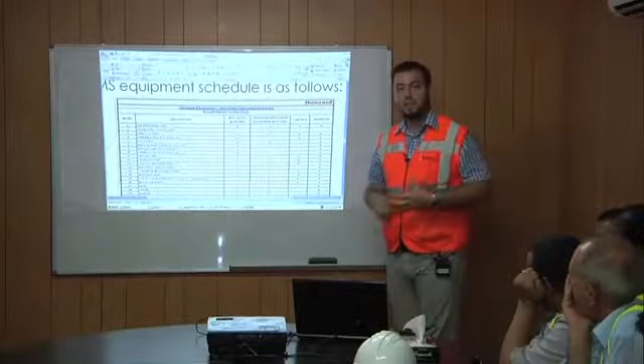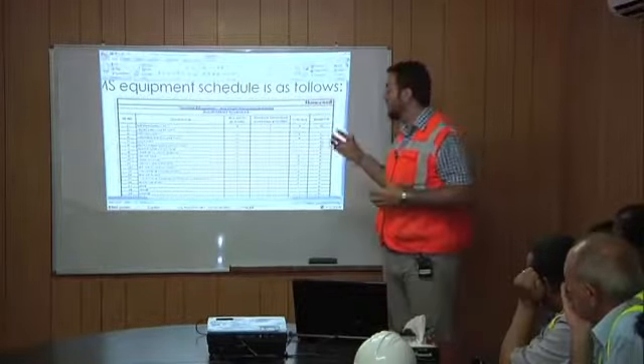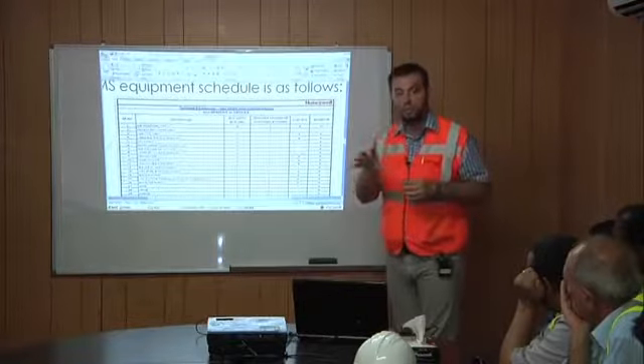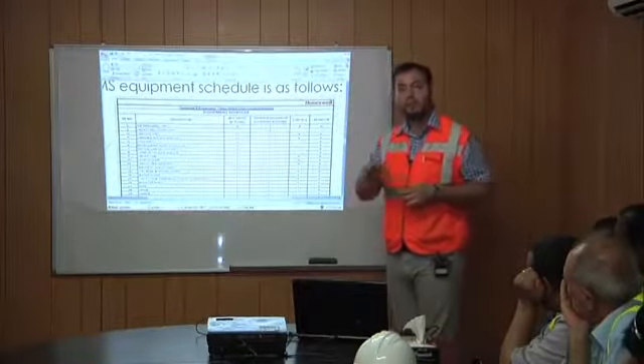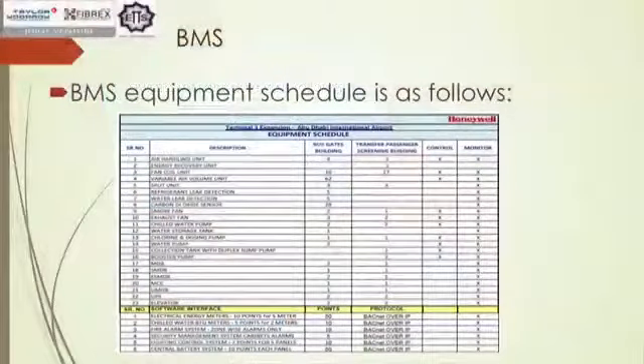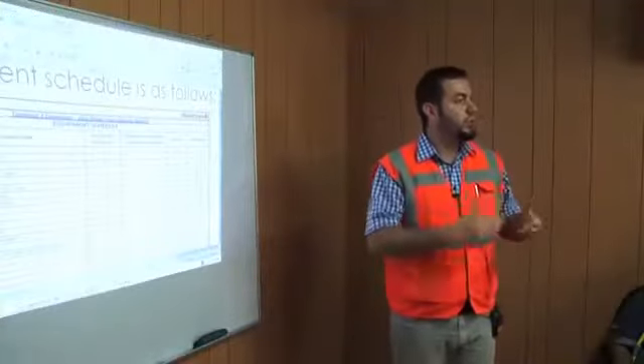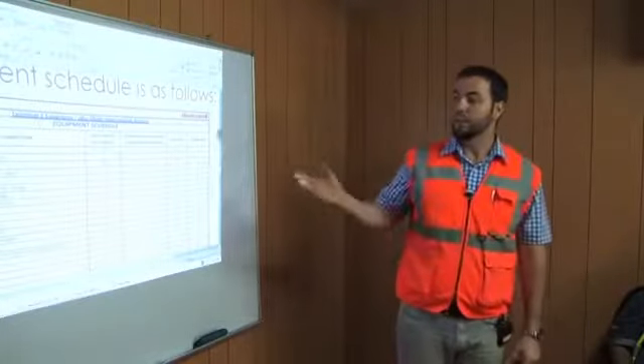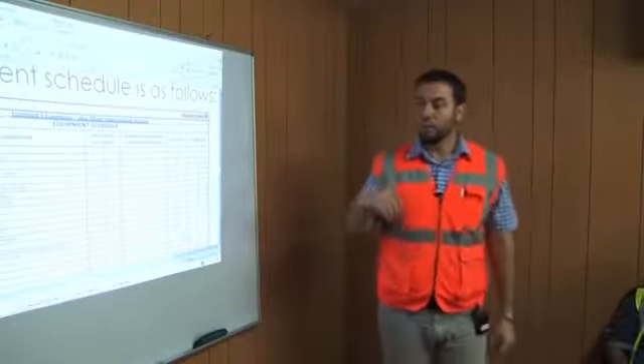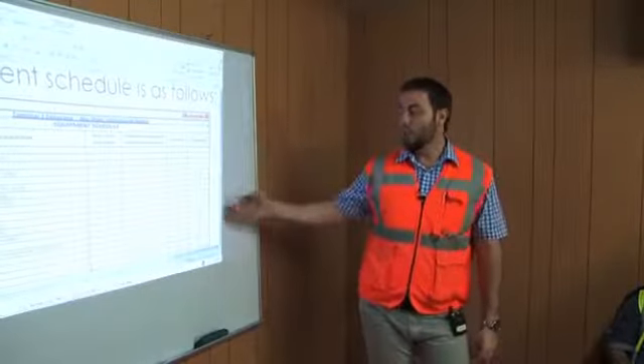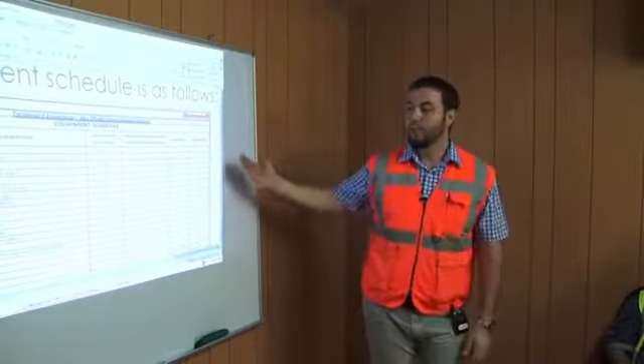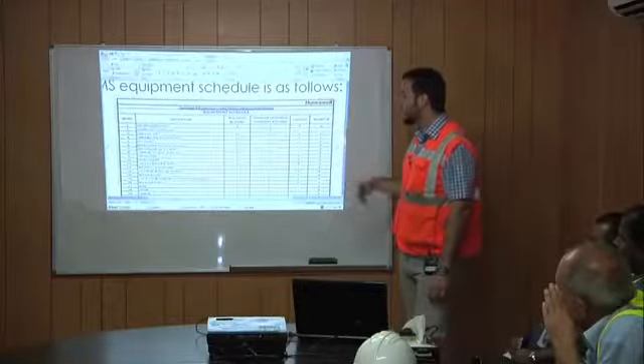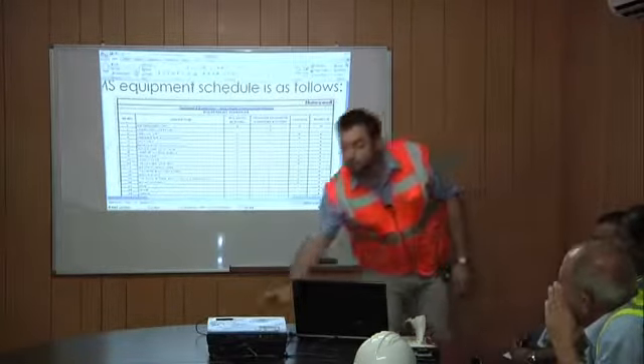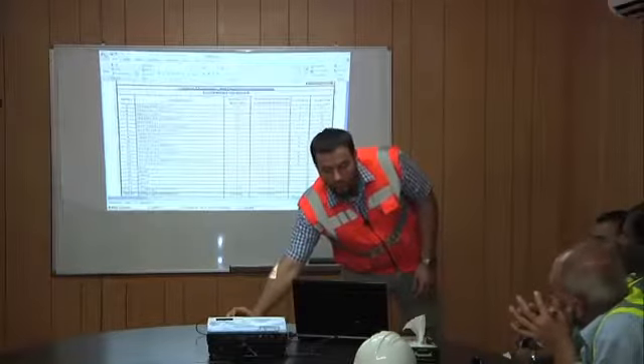Basically, the RTU will be supplying specific air, and through the BMS, you can control each zone, how much you want the temperature there. By such, you're affecting the VAV. The VAV will send signals to the RTU unit through the BMS to decrease the fan speed, which in turn decreases the temperature in our system. We've got the exhaust fans, the smoke fans, the chilled water pumps monitored. You can increase, you can decrease. We've got the water pumps, collection tanks, the booster pumps. All the DBs are monitored, whether we have a fault.